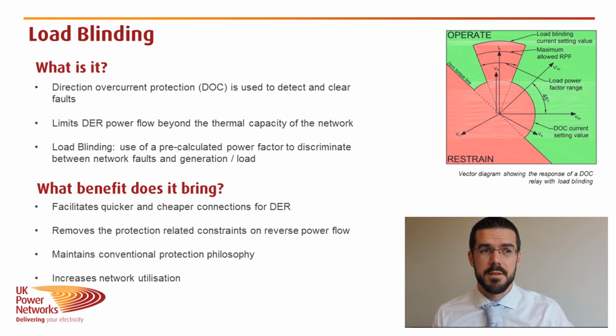Load blinding is a protection technique that leverages the significant difference between load or generation power flow and fault power flow. Specifically, these have different power factors, meaning that a modern protection relay that can measure and analyze the power factor can reliably distinguish and discriminate between network faults, which is times when you want the protection to operate so that the fault is cleared safely, and generation or load, which is when we want the network to remain connected so that the power can flow from the generators to our homes.